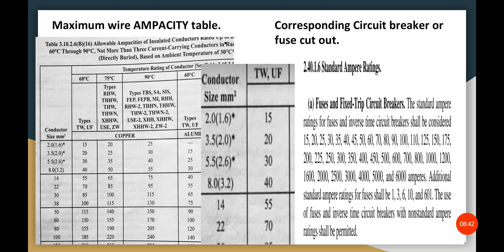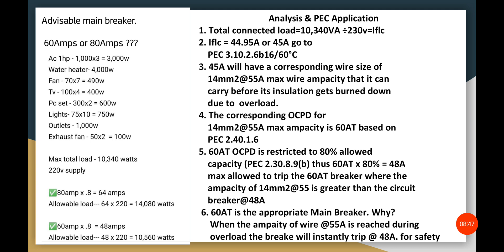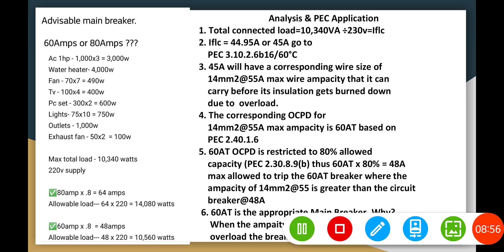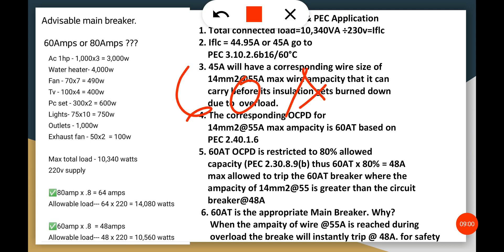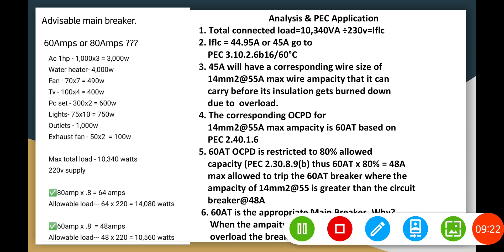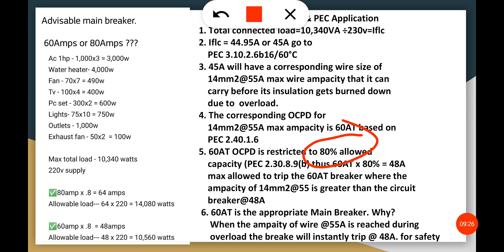To summarize so far: the wire size is 14mm² and the breaker size is 60 amperes. The maximum wire ampacity is 55 amperes. Now let's analyze the 60-ampere breaker further. Since breakers are enclosed, per PEC 230.8, only 80 percent of the rated current is allowed. So 60 amperes times 80 percent gives us an allowable ampacity of 48 amperes for the breaker.